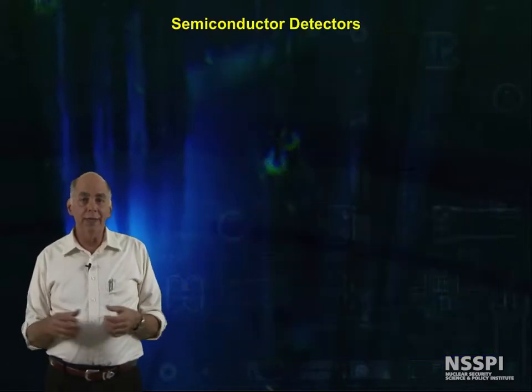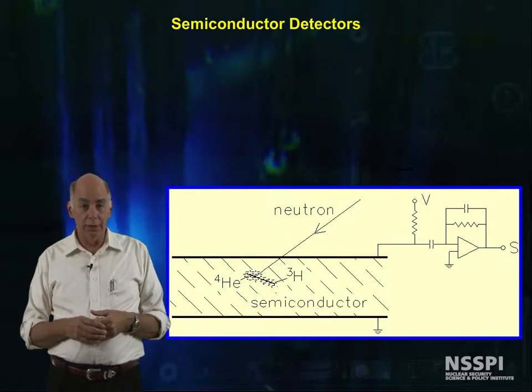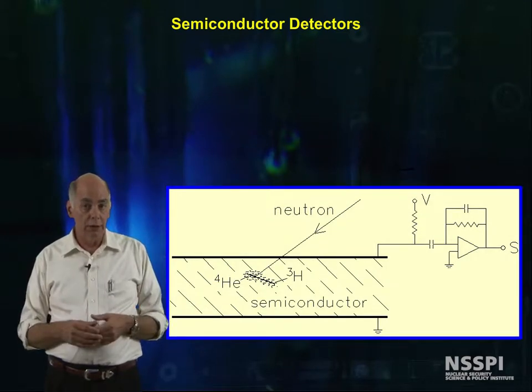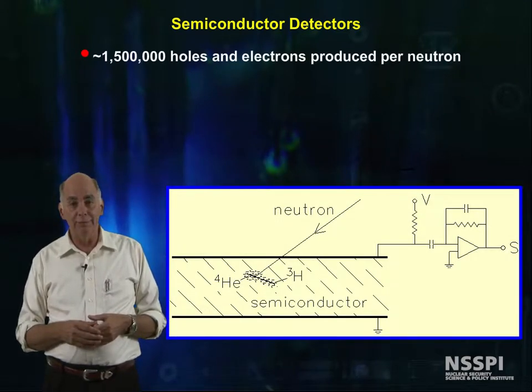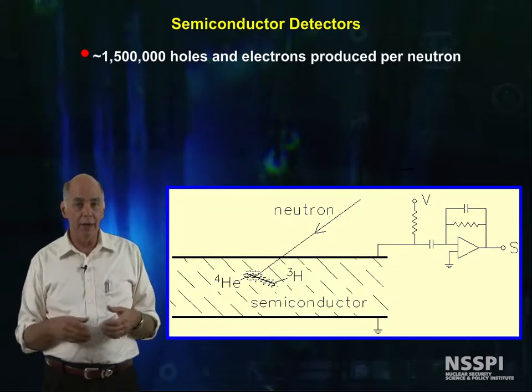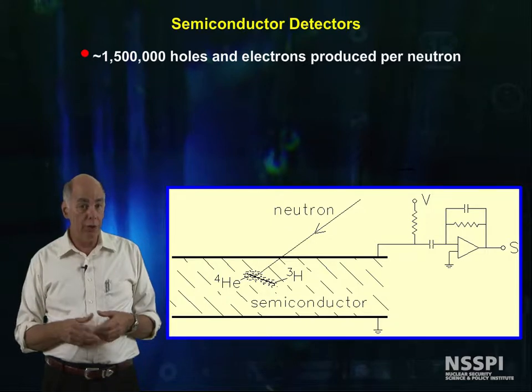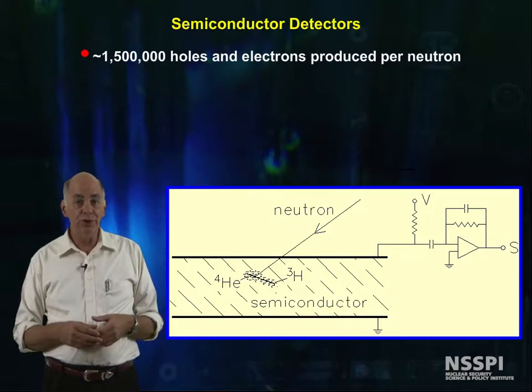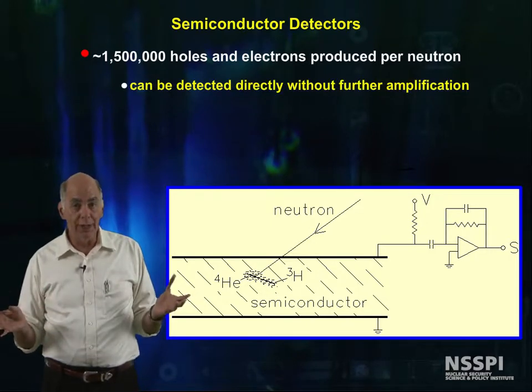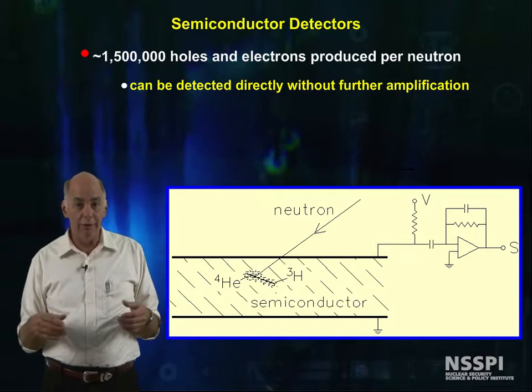We can also use semiconducting materials to build a detector for neutrons. The good news about this type of detector is that you have about 1.5 million hole-electron pairs produced per neutron interaction. This signal is so large that it can be detected directly without further amplification.